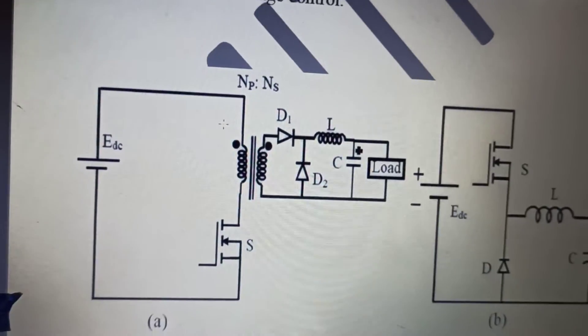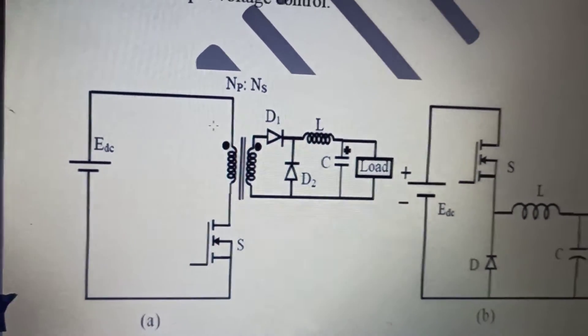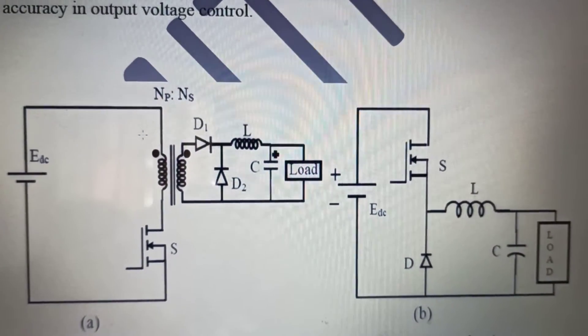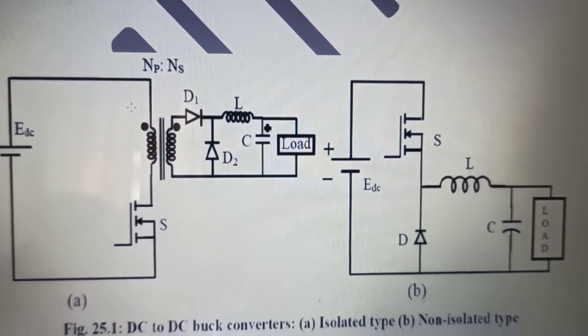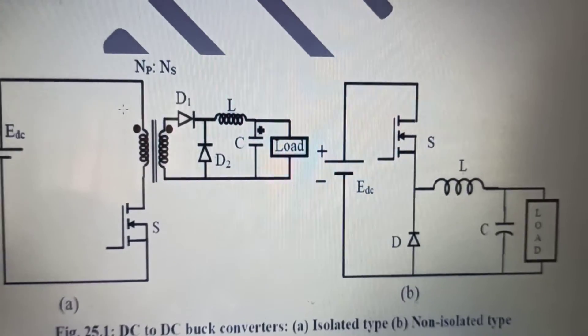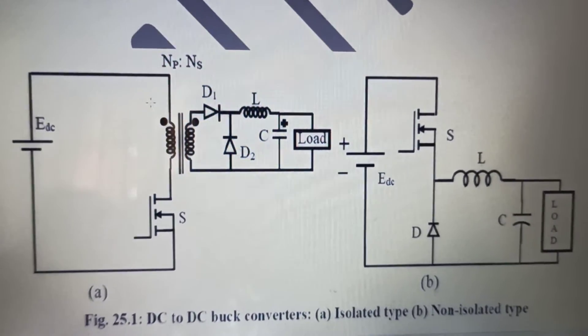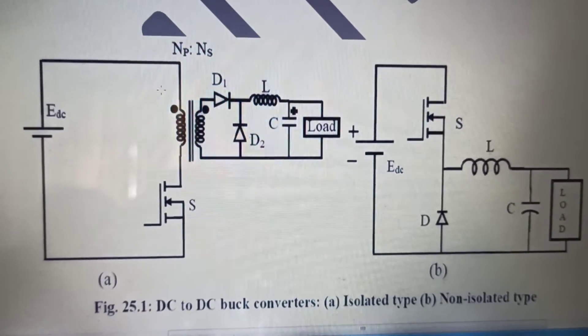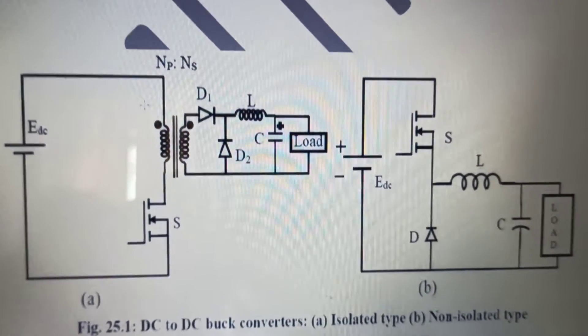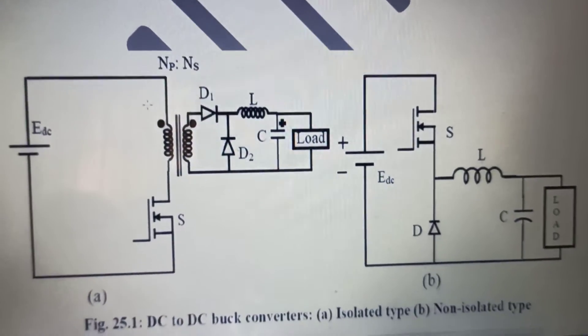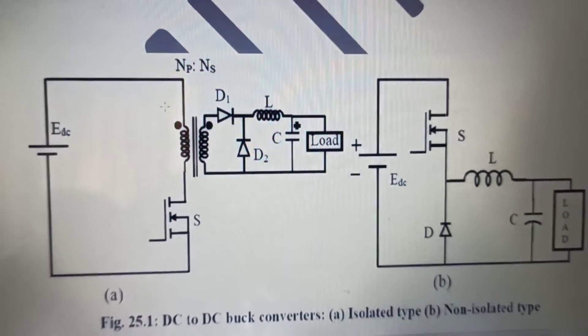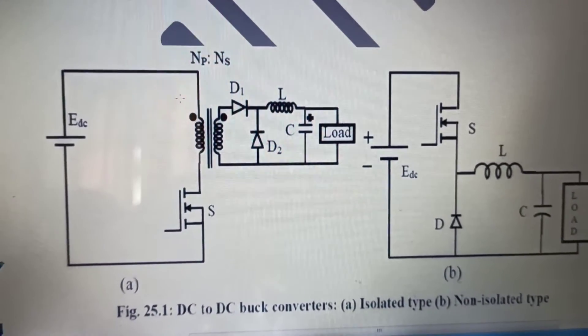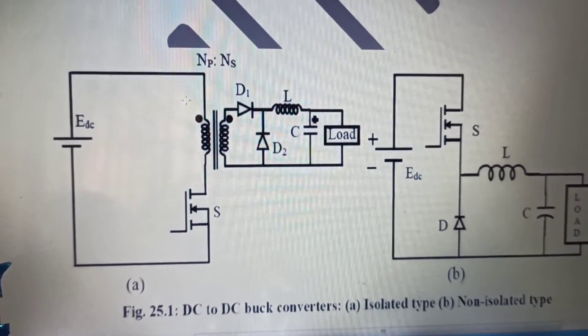But the only case is that we will not let the transformer get saturated. We will work in the linear region. Because if the transformer gets saturated, then from the BH curve, we can very well know that even for a very small increment in magnetic flux, a large amount of current will be drawn if we are operating the transformer in saturation. If you want to increase the flux by a very small value, that is phi and i.